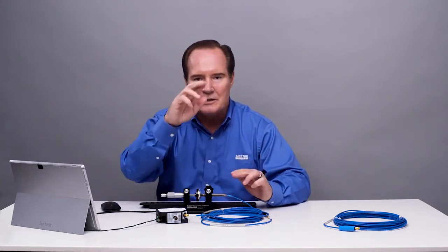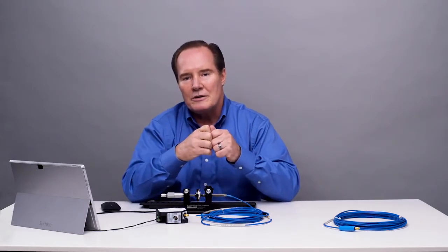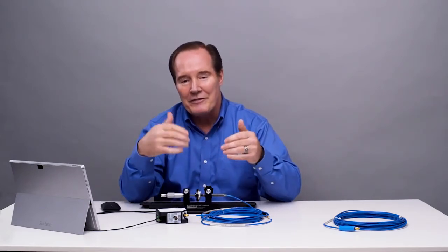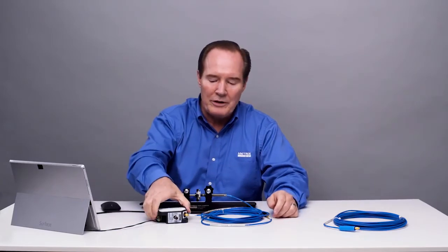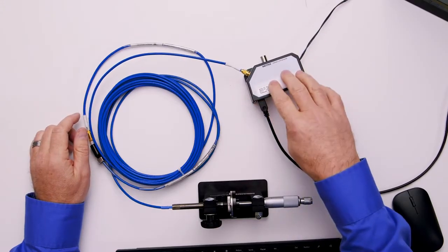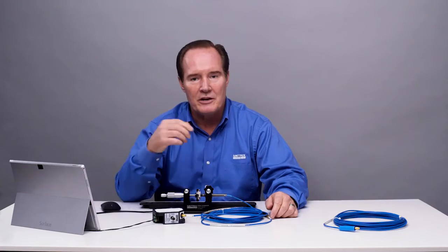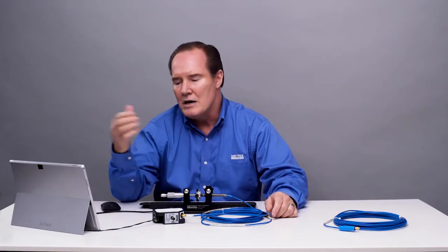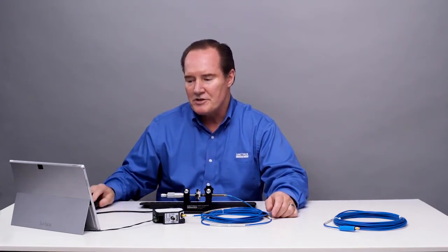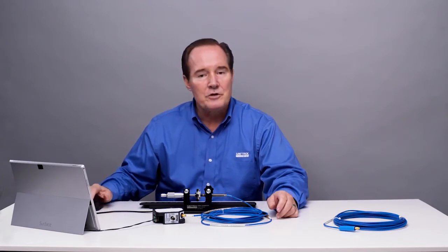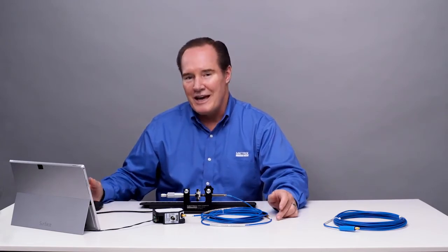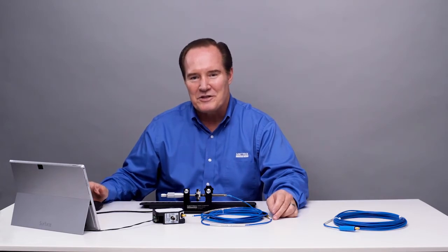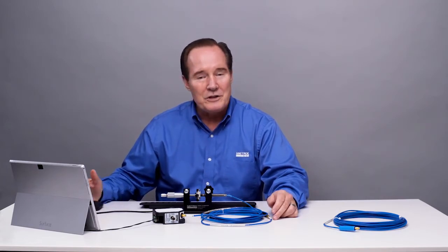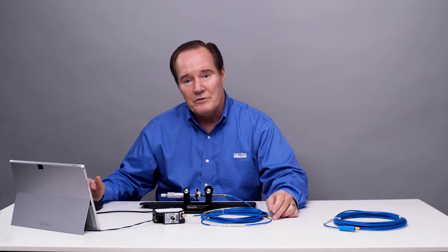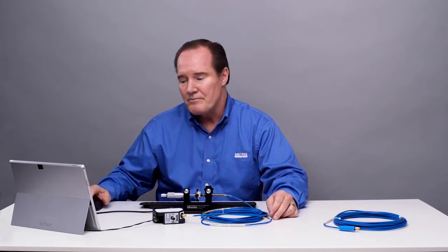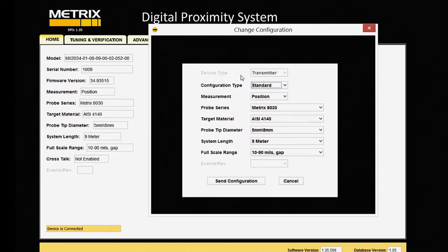So now you have a nice clean appearance in the cabinet, and it will look very nice, but now we have to make it work. The way we do that is we reconfigure the digital proximity system to that length and we check it for linearity. That's what we're going to do now. We had a 9-meter system installed and we cut off 2 meters of physical length. That doesn't mean that's the electrical length of the system. So we do have to do a verification after we've trimmed a cable and put on a new connector. So let's go in and change the configuration.